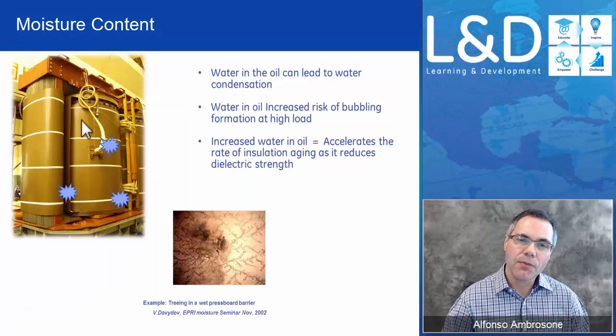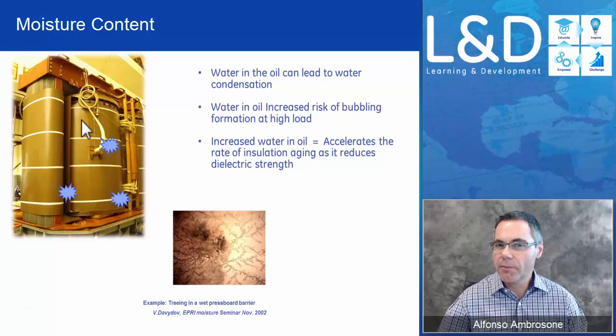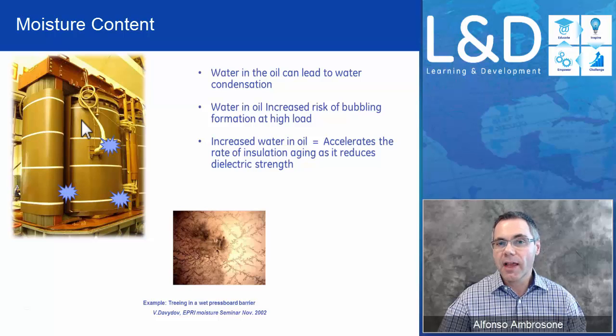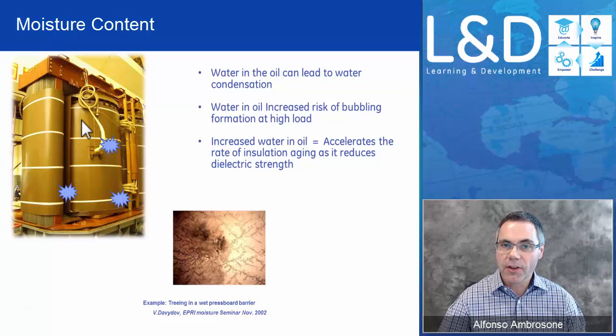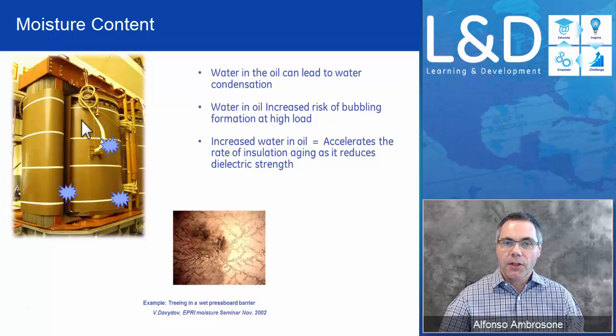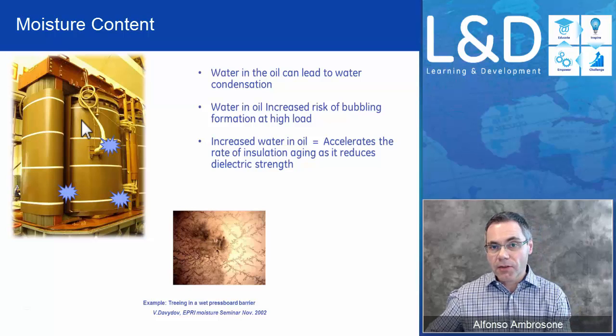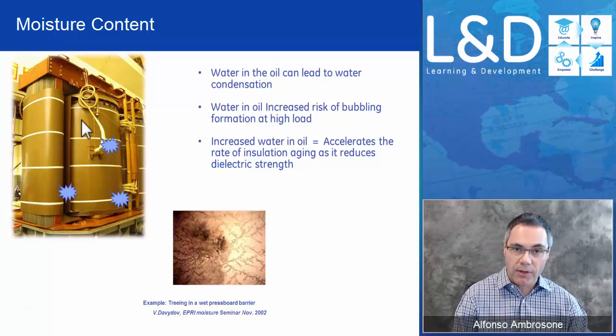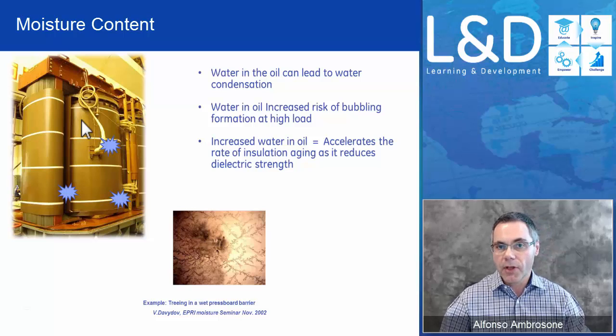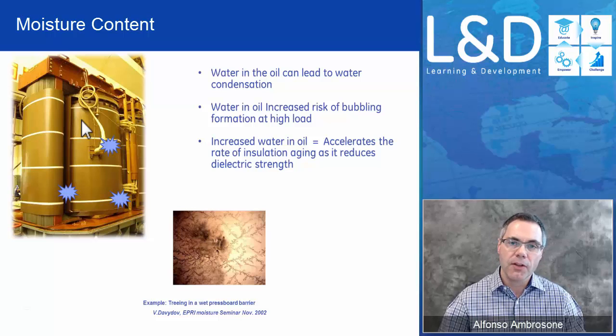Is moisture critical? Absolutely. Breakdown of paper generates moisture, and a breakdown of paper weakens the dielectric strength of the paper. Weakening the dielectric strength causes short circuits, which leads to partial discharge and will eventually lead to the aging of the transformer. The aging of the transformer is directly related to the health of the paper. This is why monitoring hotspots and monitoring the moisture in the oil is a critical part of transformer monitoring.